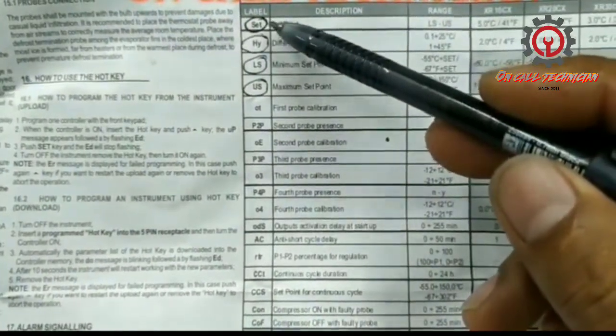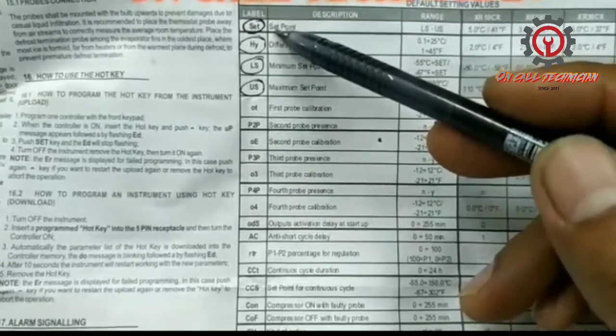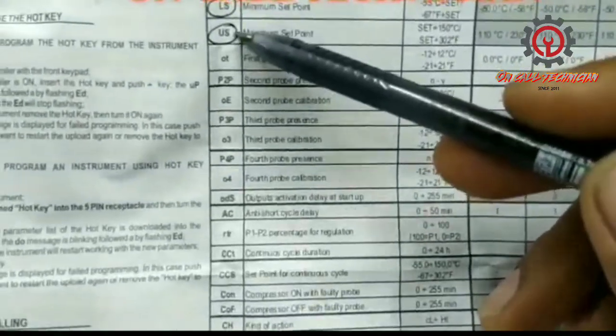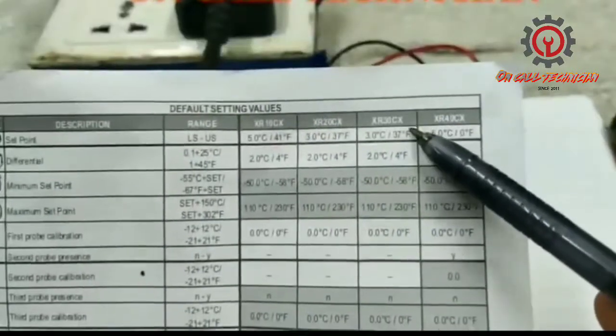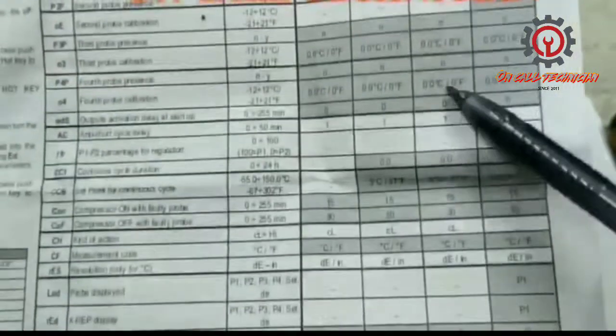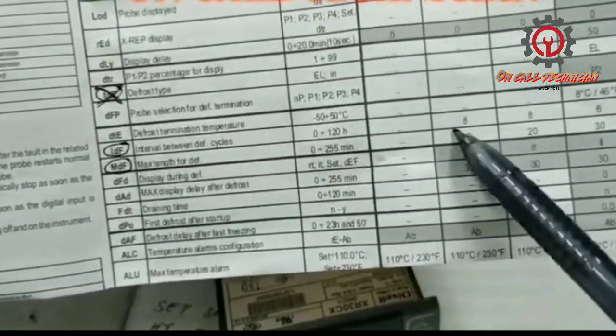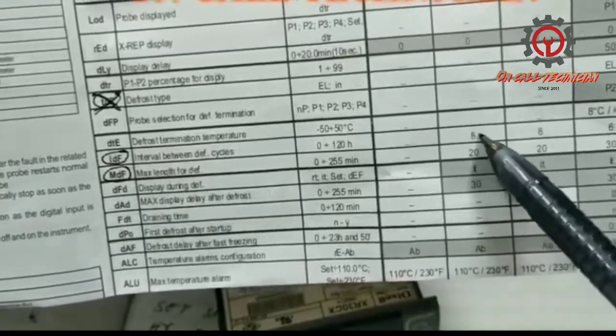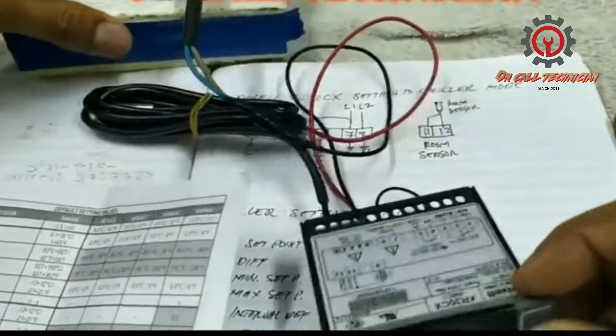The parameters you're going to program: first is the set point, which is the desired set point; next is HY differential; then LS and US. Then there is the defrost setting. For the XR30CX, it has a program for defrost — the purpose is that the compressor stops during defrost — but it doesn't have an output relay for a defrost heater. So this is why it's only intended for a chiller setting.